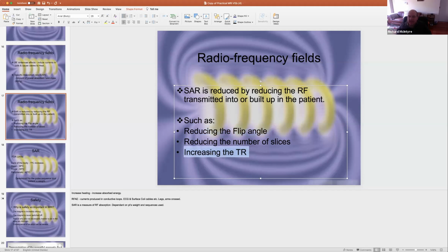We can also increase the TR. So instead of putting in radio frequency like that, we put in radio frequency over a longer time, and that gives the cells a little bit more time to relax their energy, or to give off that heat. It reduces the SAR, the specific absorption rate. So there's a range of things that we can do, including field strength.